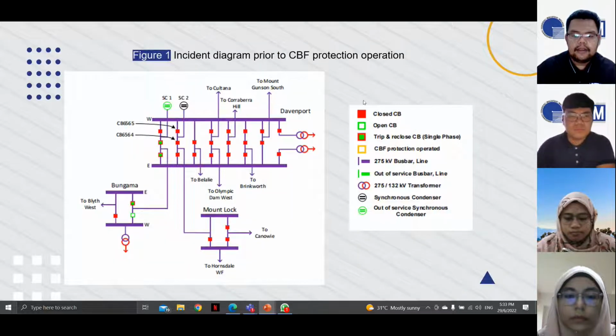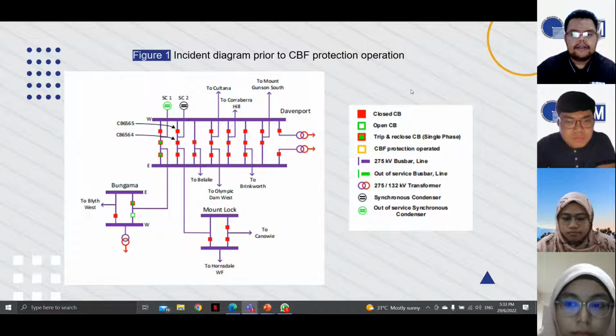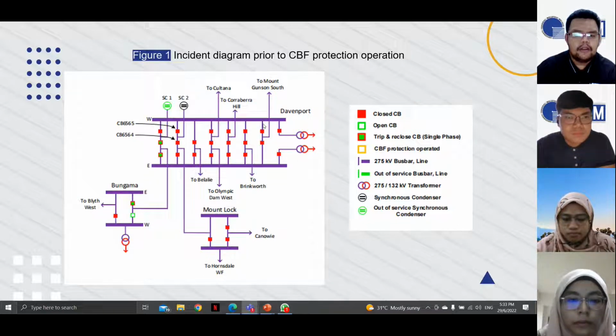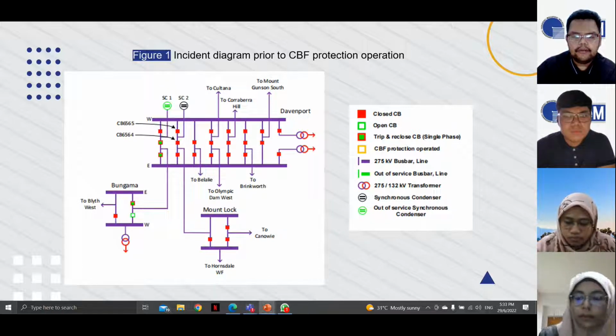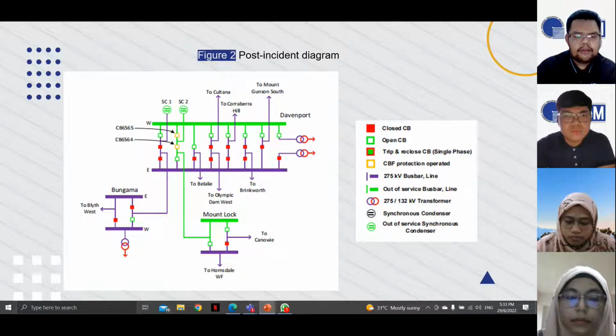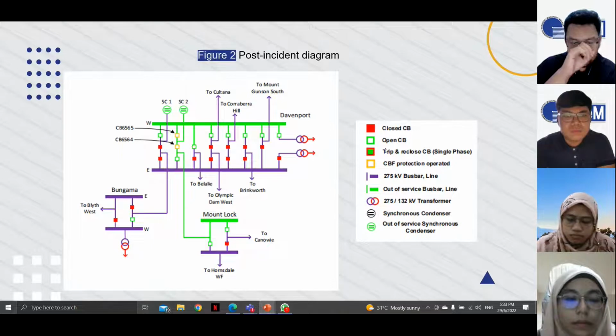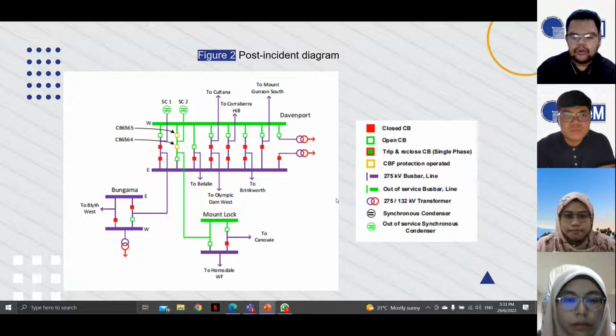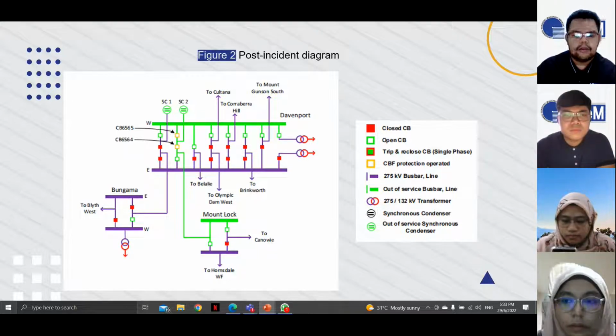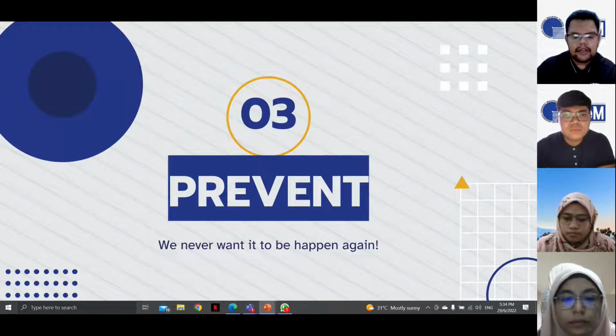Okay, here is the incident diagram prior to the CBF protection operation. So here are CB6565 and CB6564, which according to the report failed to operate correctly. When the incident happened, CB6564 turned to open, causing the other circuit breaker here to be in open condition too. So this is the circuit diagram for the incident that happened at the Davenport power plant. Here I will pass to the next presenter, Nurul Atira.